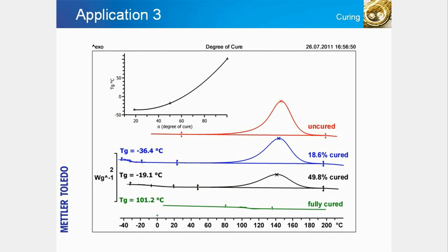Another important application of differential scanning calorimetry is to measure the curing reaction and glass transition temperature in epoxy resin systems. The diagram displays DSC curves of several samples cured to different extents. The results show that with increasing degree of cure, the glass transition shifts to higher temperatures and the enthalpy of the post-curing reaction decreases. In the diagram, the degree of cure increases from top to bottom, from the red curve of the uncured sample to the green curve of the fully cured sample.